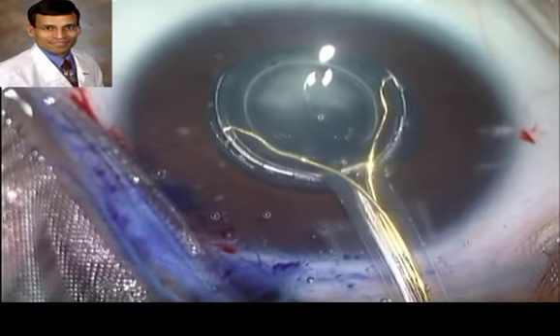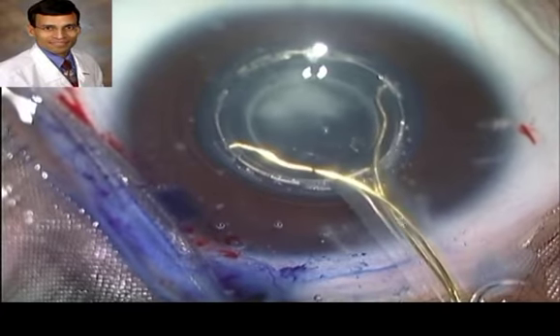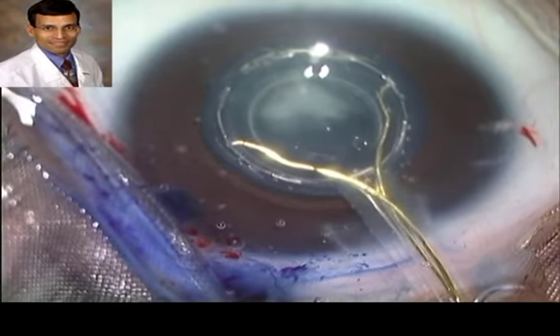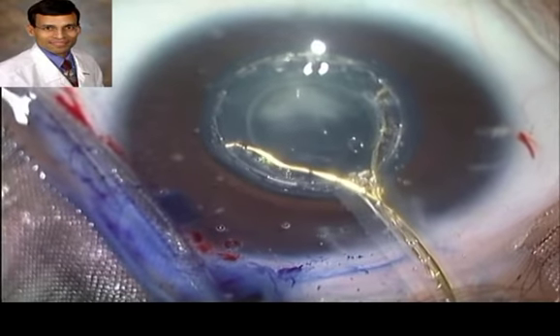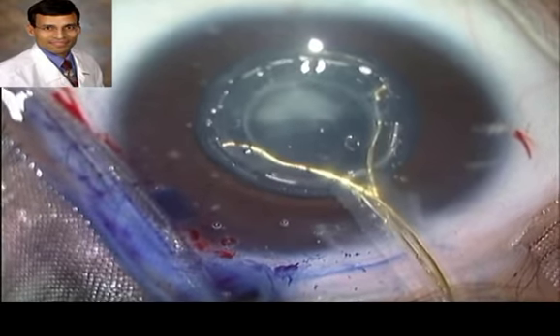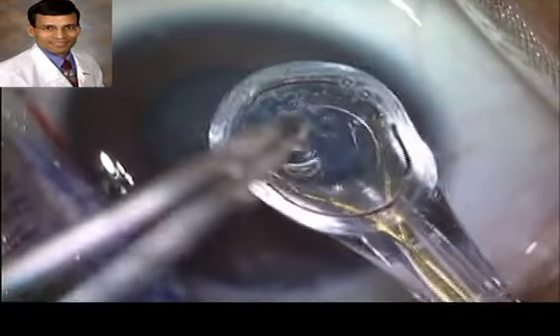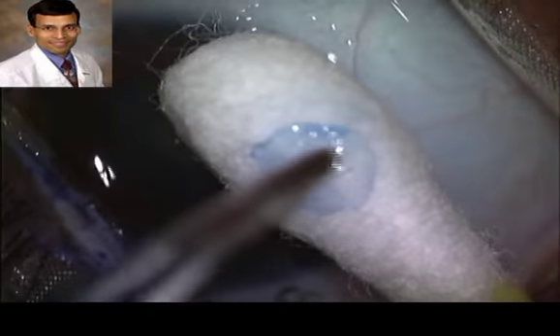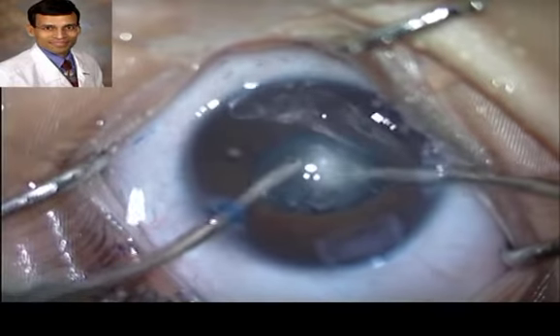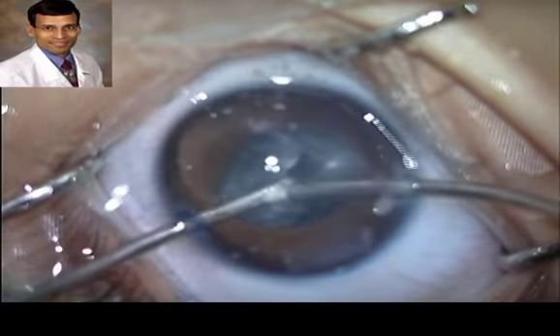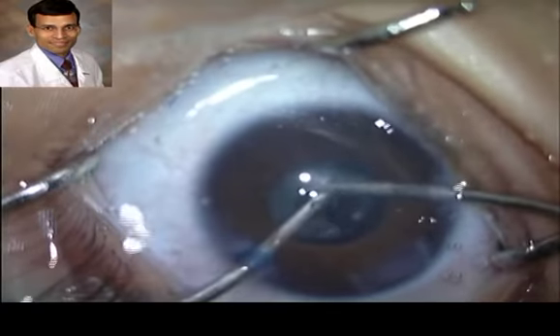Once we are satisfied with the position and the centering of the ring, we apply suction through the console of the Zepto machine. After the suction is applied, nanopulse technology is delivered, which causes vaporization of the water molecules trapped between the capsule and the nitinol ring, and this causes a perfectly centered smooth rhexis in one go. Unlike the femto, the laser pulses are not applied sequentially, and the 360-degree rhexis is achieved in one shot.